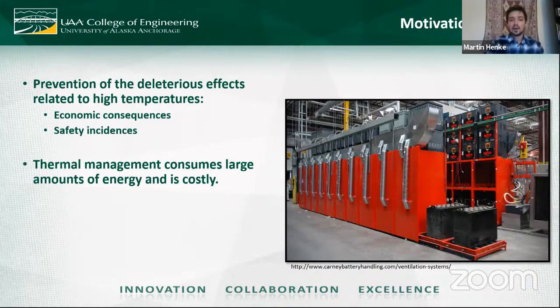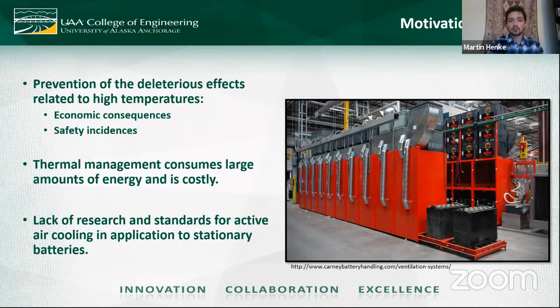But continuing thermal management can be extremely costly for large stationary battery systems. Placing batteries in a room and then cooling the entire room is obviously not a very efficient system. If you take into account the fact that these batteries are always producing heat, it becomes evident that a huge amount of energy every year is devoted to simply managing these batteries' temperatures, and doing it quite ineffectively. And then finally, there's been a lack of research on how to effectively implement active cooling for the purpose of keeping stationary batteries cool.